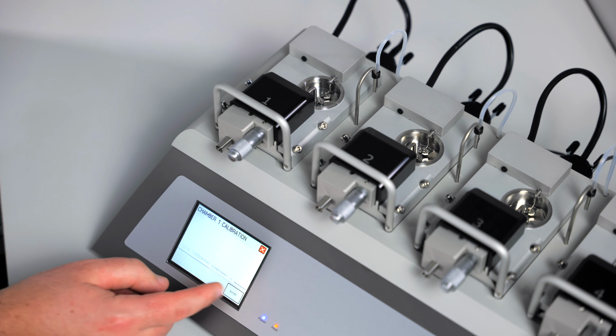Step 1 tells you to follow the procedure in the manual. However, instructions will also be provided on the touchscreen. Press next step. Step 2 tells you to place the calibration bridge and T-balance on the chamber that you will be calibrating.